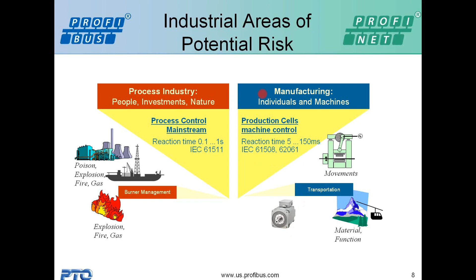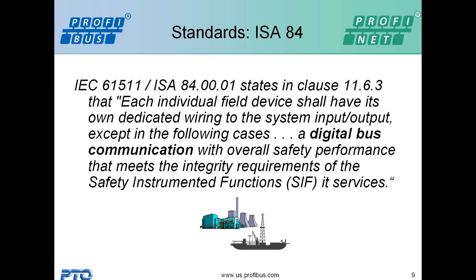On the process side, the standard is IEC 61511, which has been adopted by ISA 84, and it states that each individual field device shall have its own dedicated wiring to the system input-output. And if we just stop there, this would kind of be the old way, where you have to hardwire everything. But there's an exception now for the case where you have a digital bus communications, but it also has to meet an overall safety performance that basically gives you that same level of protection that you had with dedicated wiring. And there are authorities that test and specify what those requirements are.